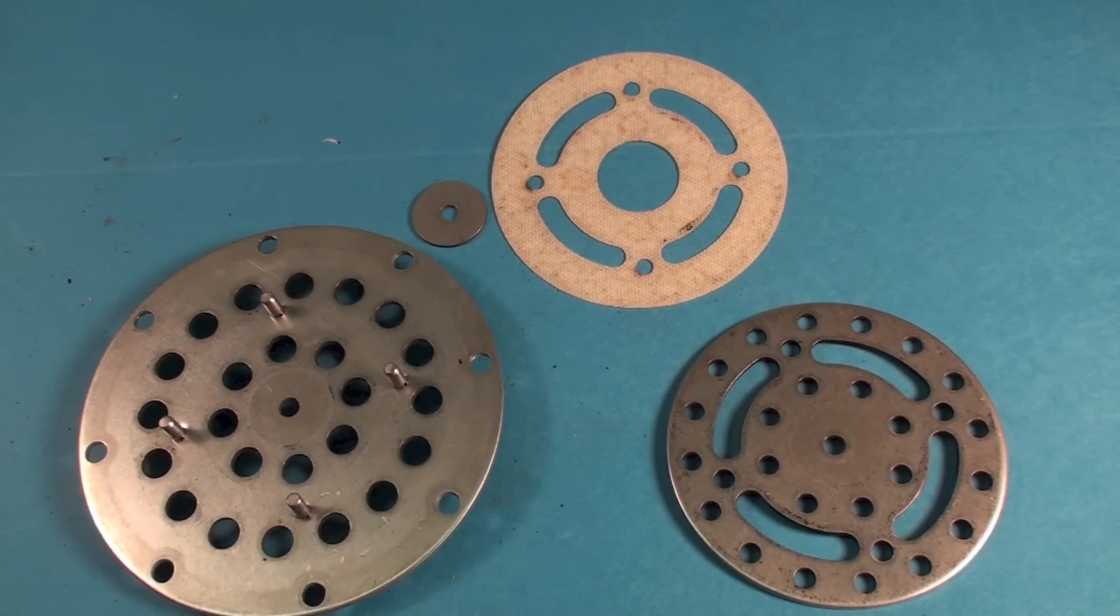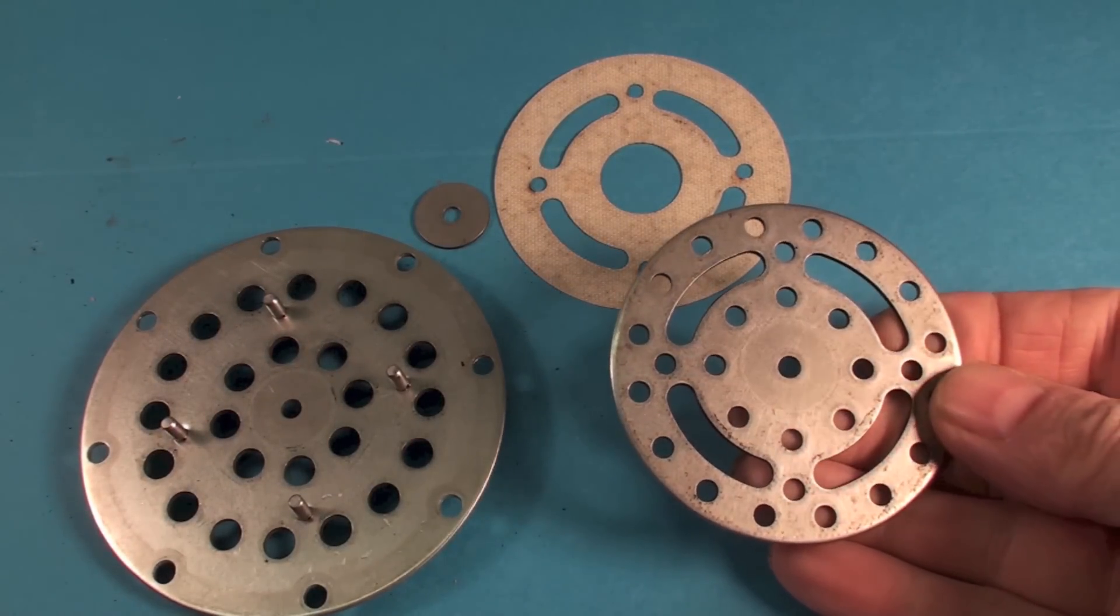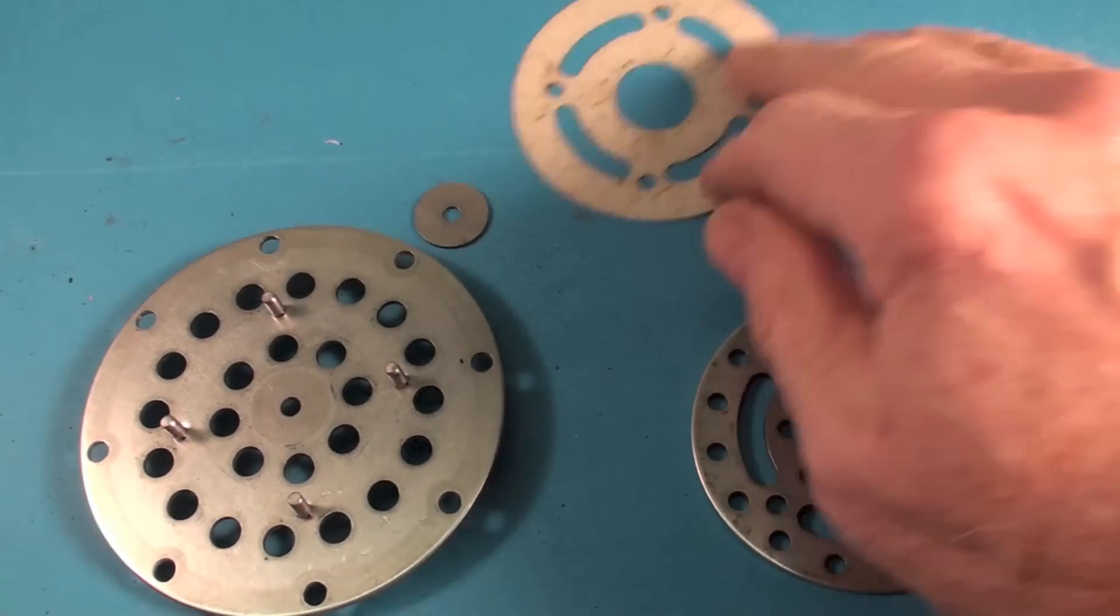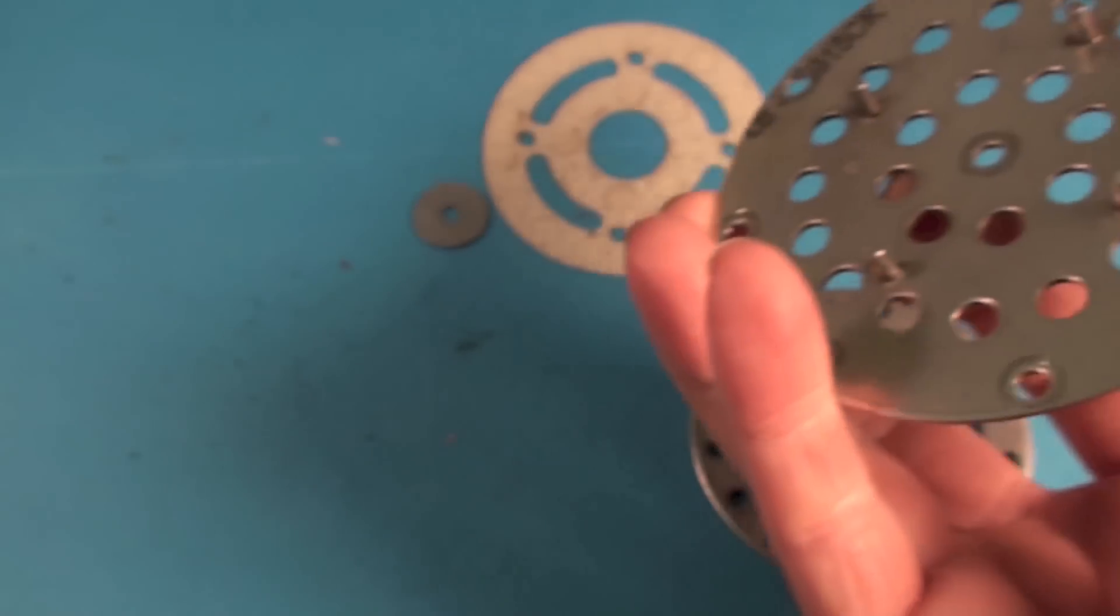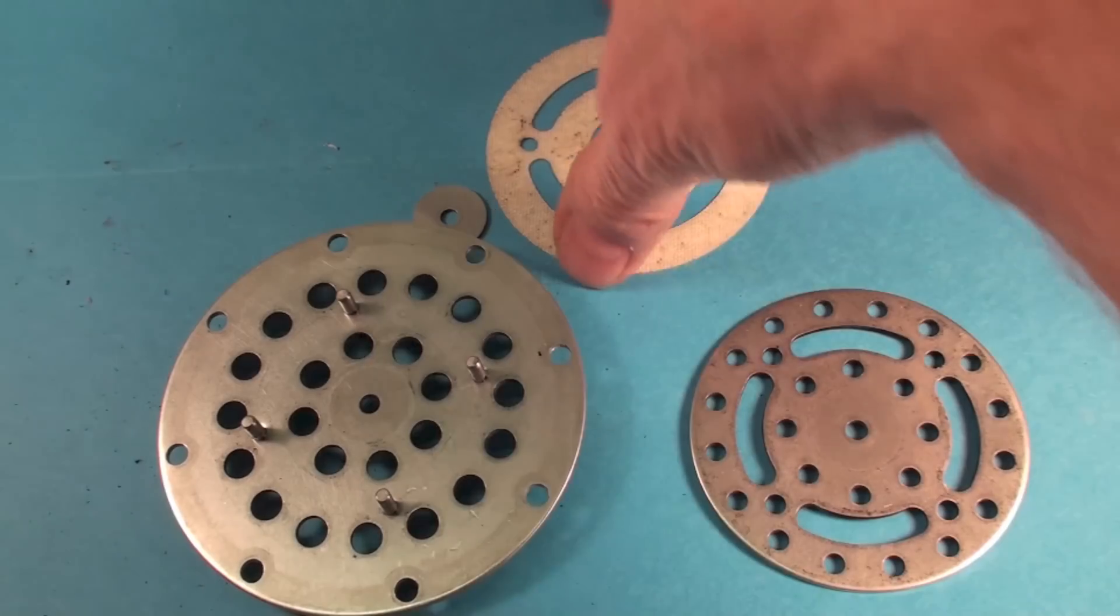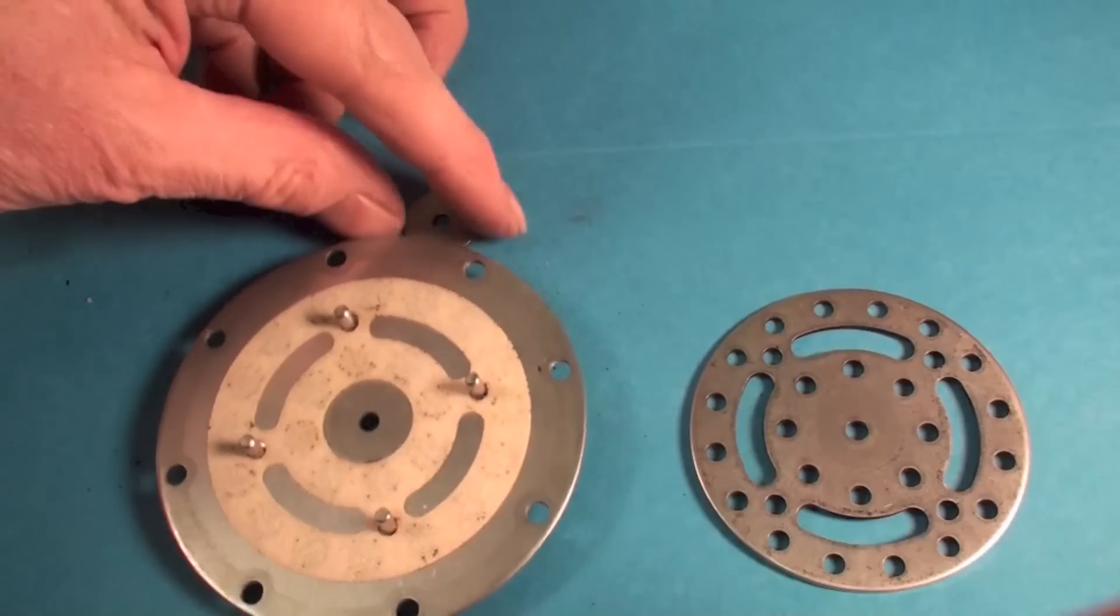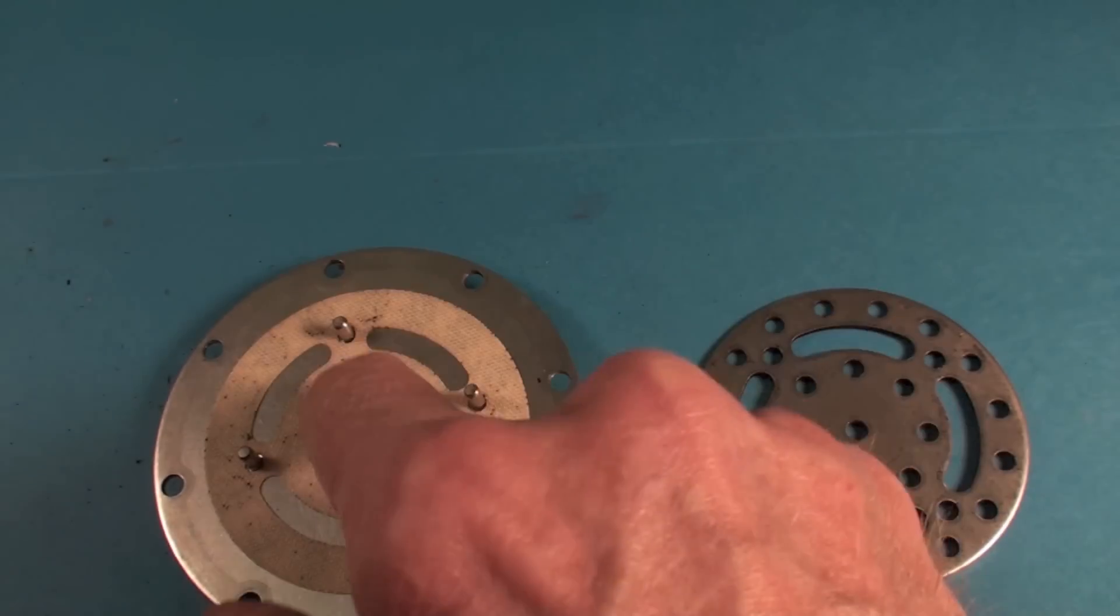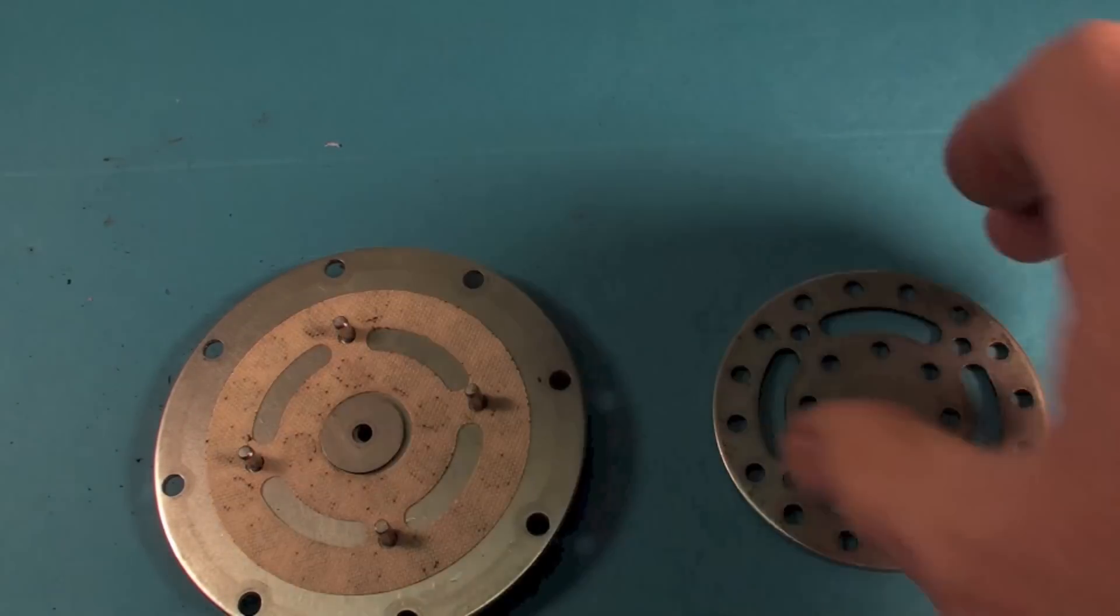Here I've taken that air flapper and kind of cleaned it up. This part right here, I've just brushed it off with soap. There's nothing special. Like I said before, this is not really repair. I would throw this away. When you put this back together, you're going to put this silly thing here and then this washer has got to be in here. In fact, there's different thickness washers for different furnaces because that's going to determine how much that flapper opens.